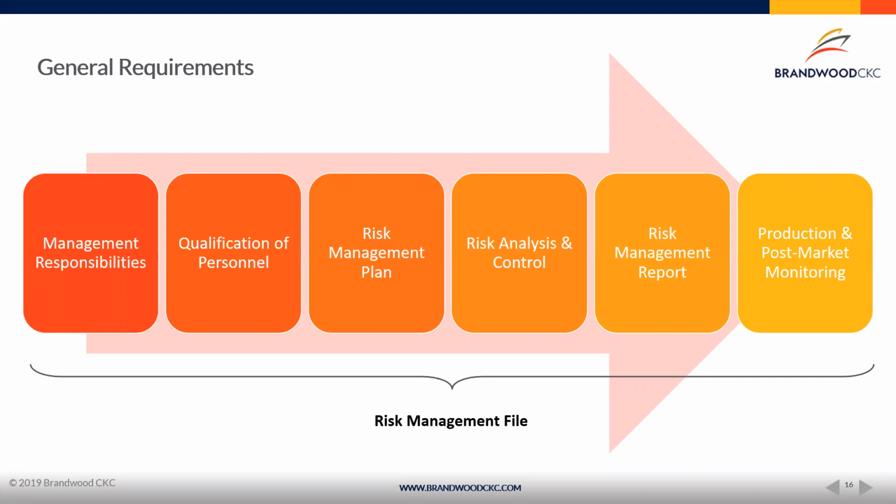You can't just put it out there and it does what it does. You have to be able to say that we're monitoring this, we're looking for when there are safety or effectiveness issues, and we're bringing that back into our device, or into our design and development of our device. It may be inconsequential, it may not be significant, but it may be something extremely significant that you need to create recalls, advisory notices, whatever. So that's the last piece in the risk management file.